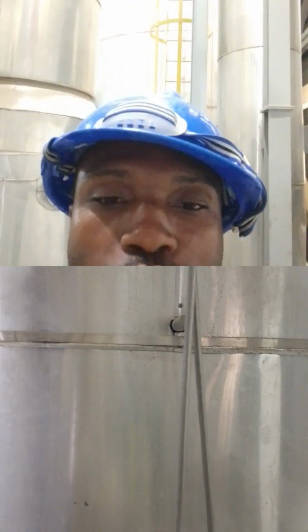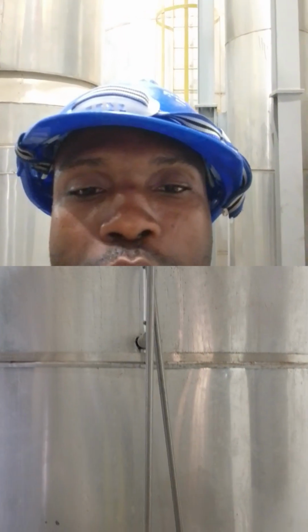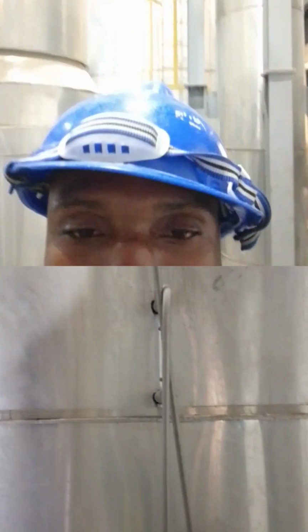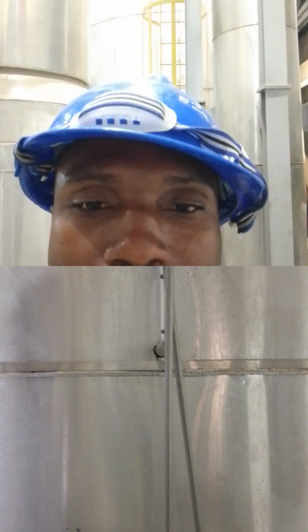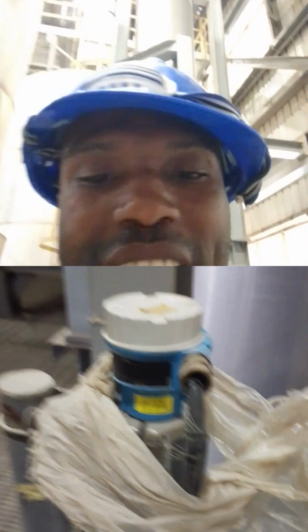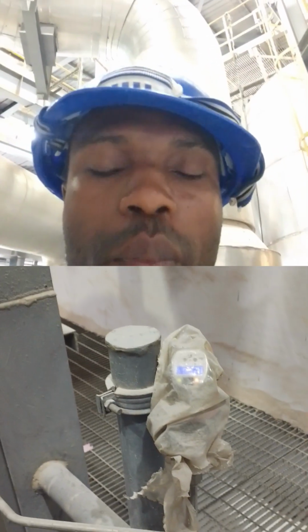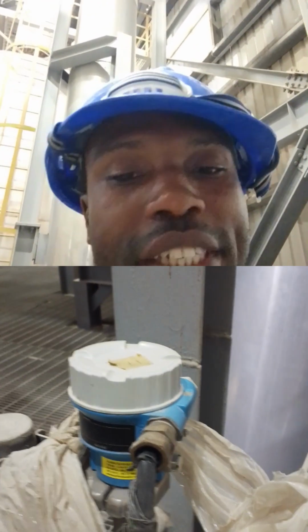measure and compare the results of the two against one another, and then help to detect whether there is a fault in any of the two devices. So the primary reason why the two of them are used on the same process equipment is in case one gets faulty, the other can be used. And then this one is the automated form of this. This one is manual, it's read on the spot, on the field, while this one transmits the results to the DCS, which is automated.